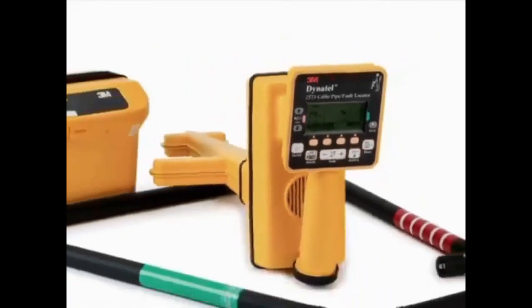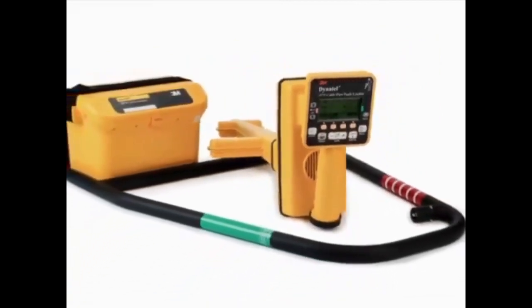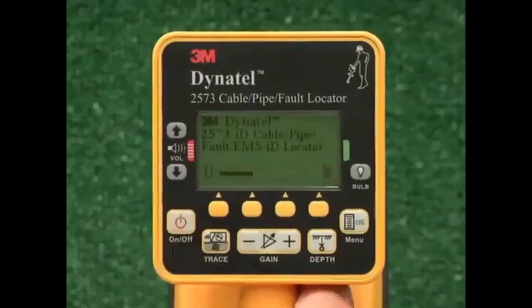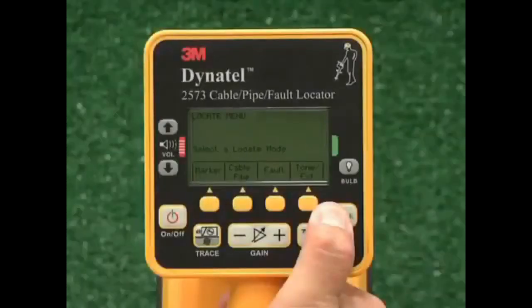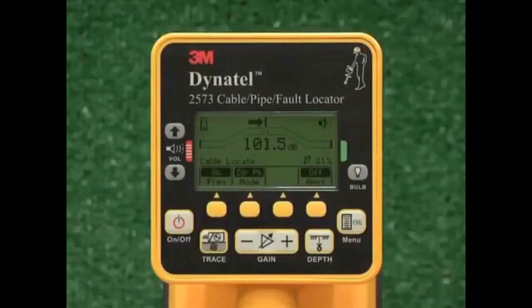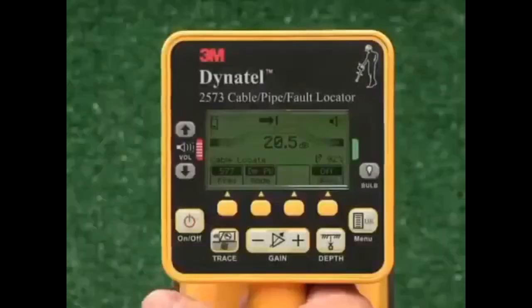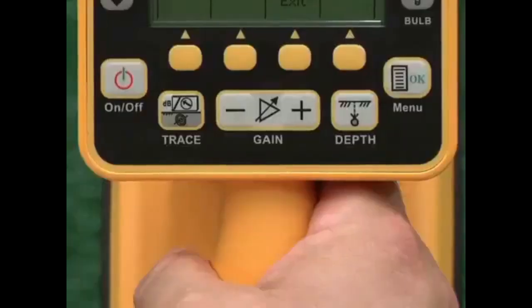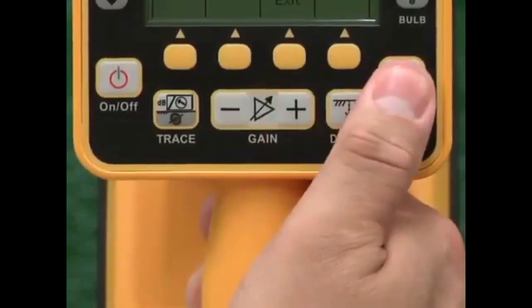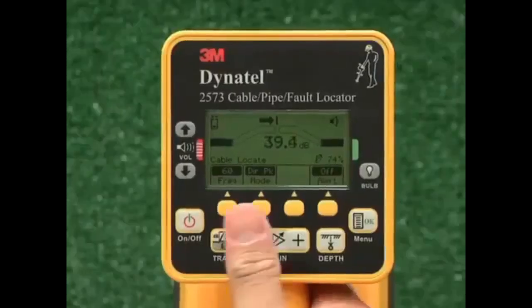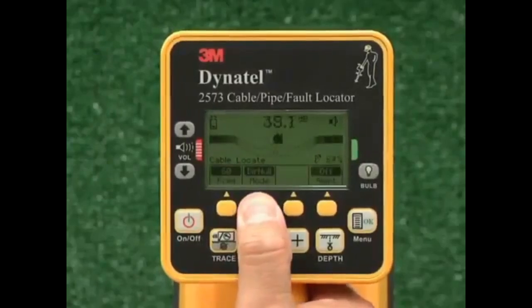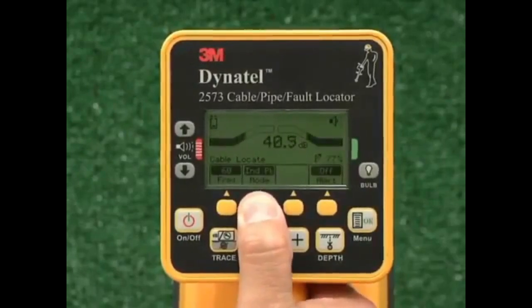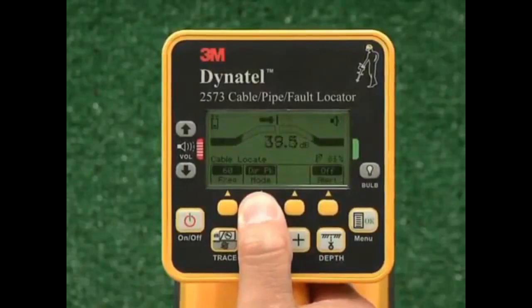Once a good signal path has been created and the correct frequency applied to the target, the next task is to detect the signal with the receiver. Turn the receiver on by pressing the power key. From the main locate screen, select cable pipe. Press the first yellow command key labeled frequency repeatedly until the transmitter frequency is displayed above this key. Press the OK key to return to the locating screen. To select the locating mode or antenna configuration of the receiver, press the second yellow command key labeled mode. Repeatedly pressing this key will toggle the receiver between directional peak mode, directional null mode, and special peak mode.